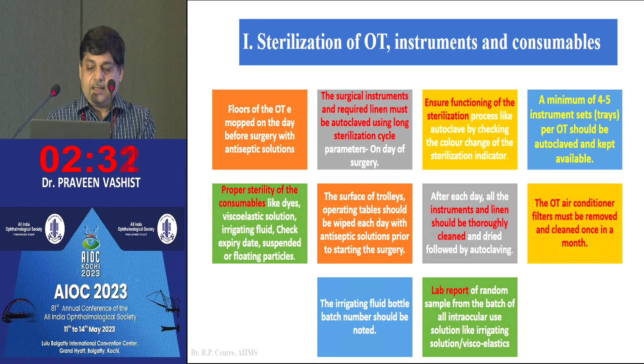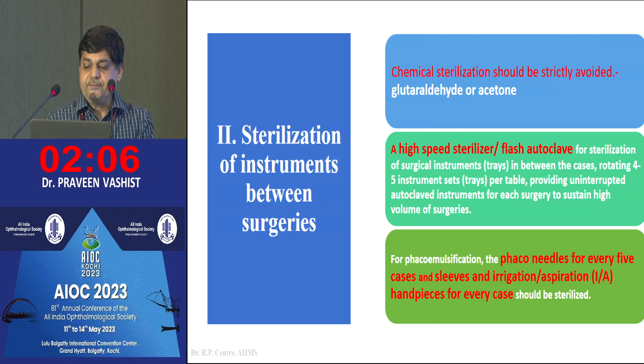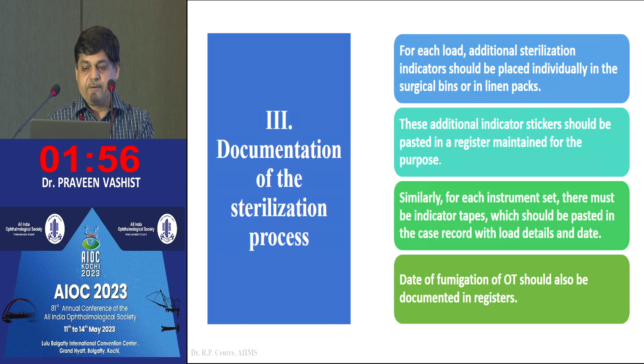And different things have been added. I think there's no need to go into detail of each and everything. In fact, for instruments, they said chemical sterilization should be strictly avoided, such as glutaraldehyde and acetone. You should use high-speed sterilization or flash autoclave for sterilization of surgical instruments in between the cases. For phacoemulsification, the phaco needles should be sterilized for every 5 cases, and sleeves and irrigation aspiration handpiece for every case. Documentation, as Dr. Harpreet has mentioned, in fact, they have given guidelines related to documentation of the sterilization process.